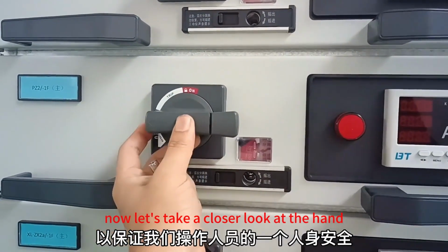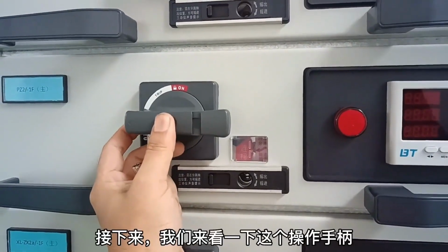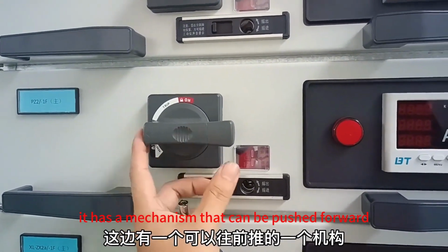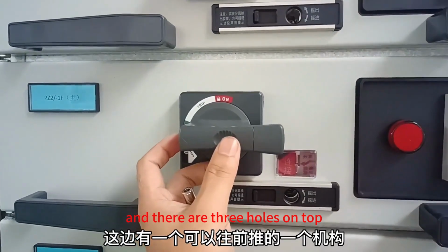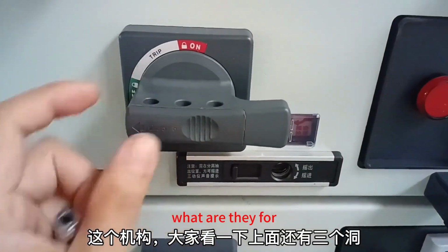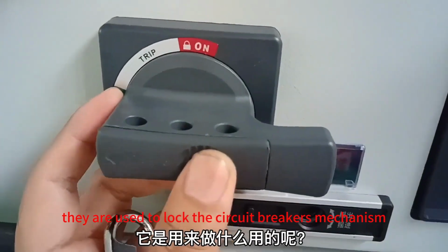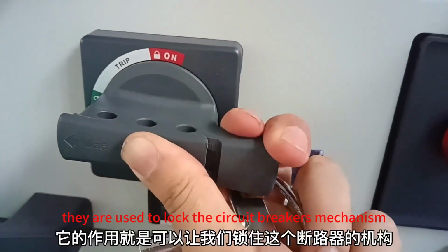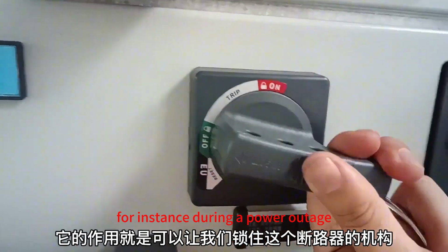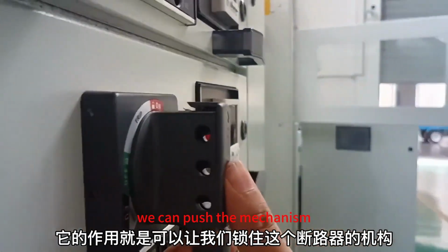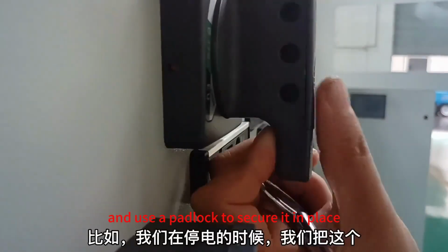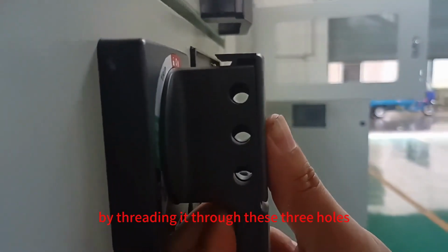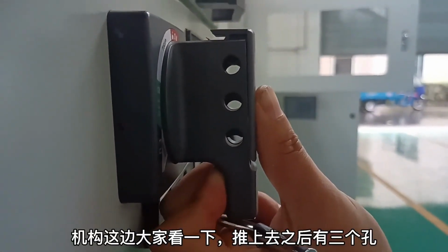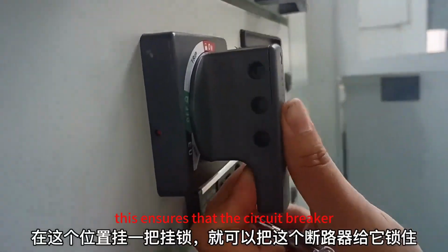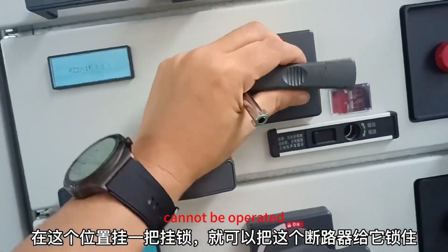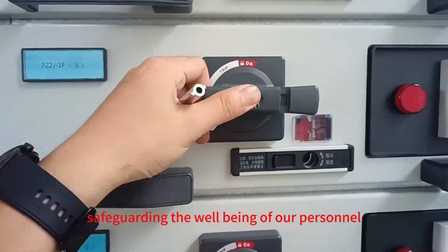Now let's take a closer look at the handle. It has a mechanism that can be pushed forward, and there are 3 holes on top. What are they for? They are used to lock the circuit breaker's mechanism. For instance, during a power outage, we can push the mechanism and use a padlock to secure it in place by threading it through these 3 holes. This ensures that the circuit breaker cannot be operated, safeguarding the well-being of our personnel.